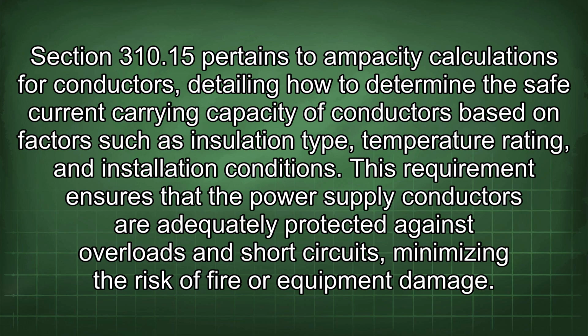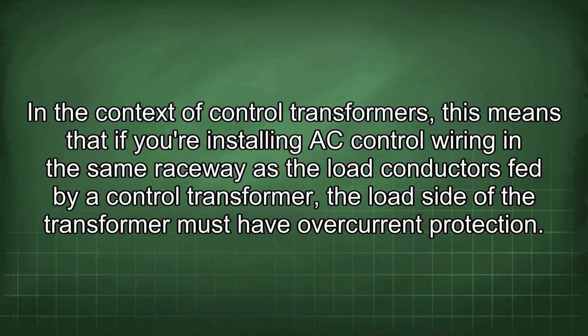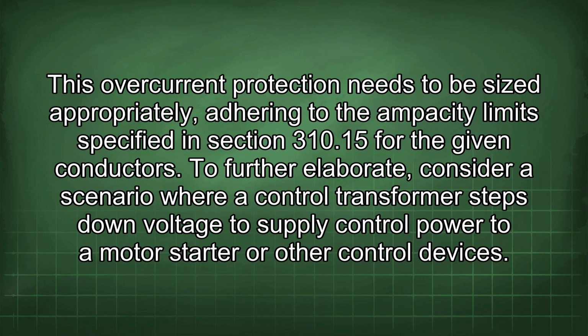This requirement ensures that the power supply conductors are adequately protected against overloads and short circuits, minimizing the risk of fire or equipment damage. In the context of control transformers, this means that if you're installing AC control wiring in the same raceway as the load conductors fed by a control transformer, the load side of the transformer must have overcurrent protection. This overcurrent protection needs to be sized appropriately, adhering to the ampacity limit specified in Section 310.15 for the given conductors.